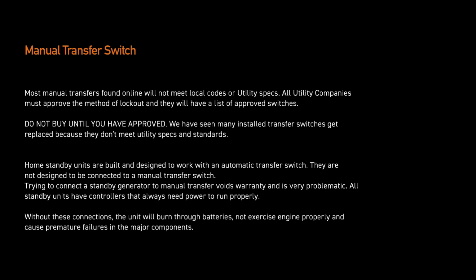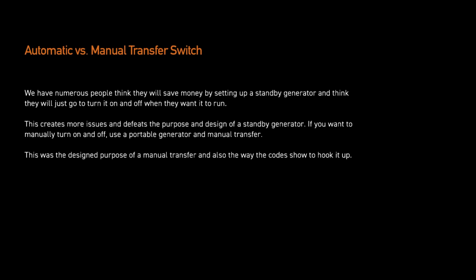All standby units have controllers that always need power to run properly. Without these connections, the unit will burn through batteries, not exercise the engine properly, and cause premature failures in the major components.